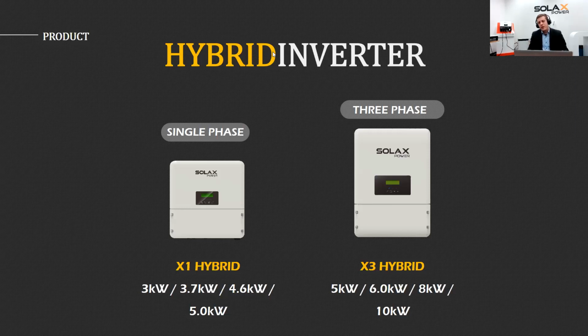The reason I say you can connect almost every battery is that in the menu of our inverters you can choose whether you have a lithium or a lead battery. If you have a battery not natively compatible with our system, you can type in its characteristics, such as charging current, discharging current, lowest voltage, highest voltage, and similar settings, so it can work with it.